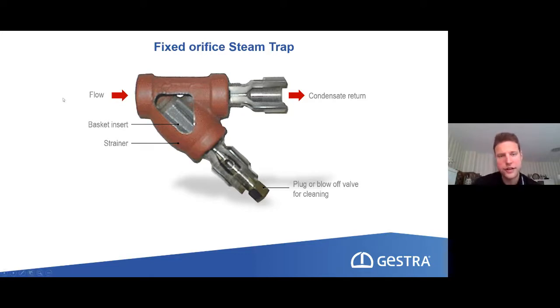So the condensate inlet is here, and then it travels through a strainer, which is very good because all we have with such a fixed orifice steam trap is this little hole here, the drilling. And this is only one diameter, always the same small diameter. And here we have the condensate outlet. If we didn't have any strainer here, we would of course get problems every now and then, because little dirt particles could block this very small orifice.